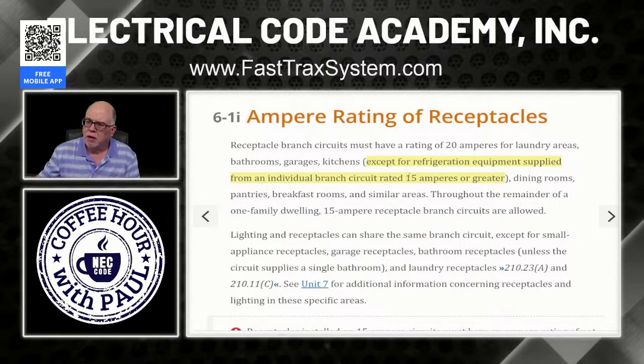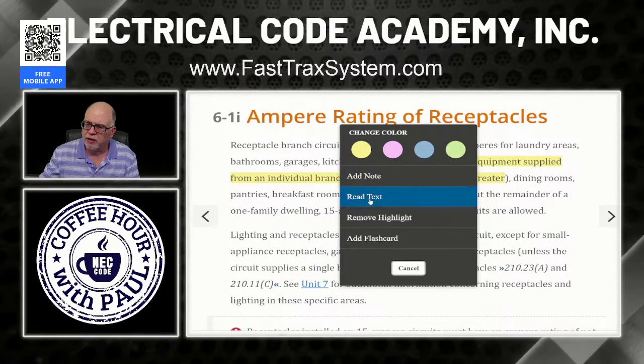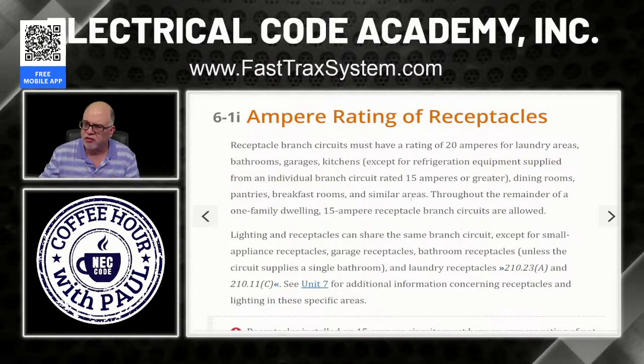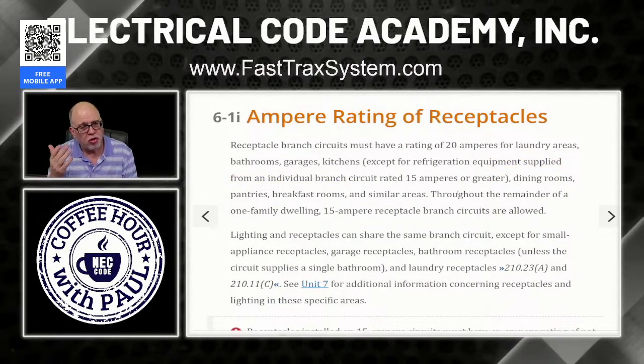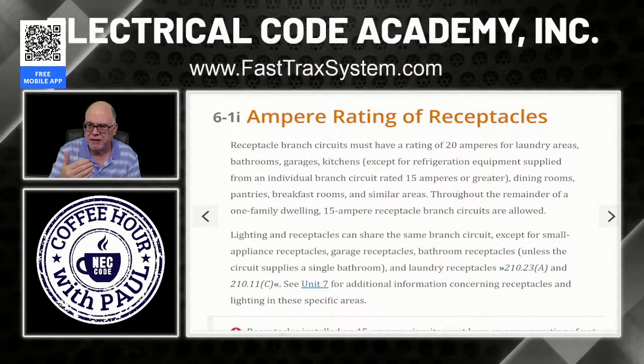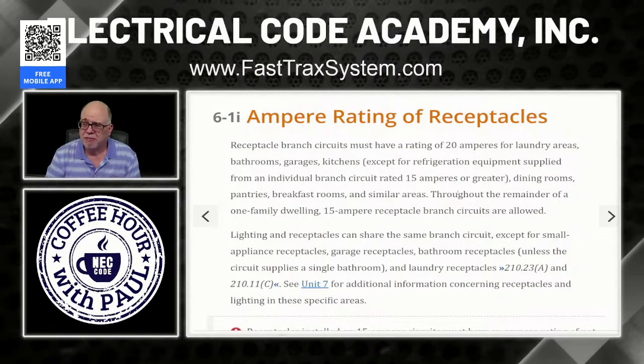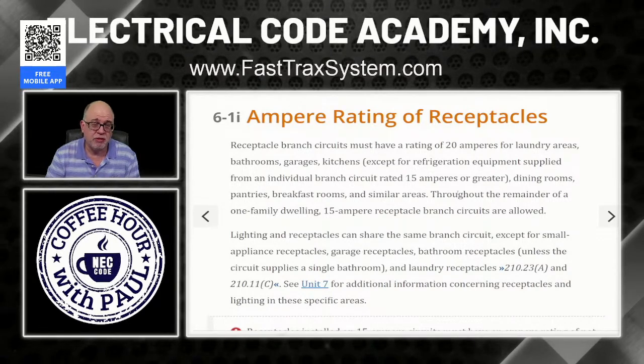Now, those are required to all be 20, except for the individual branch circuit to the refrigerator, if you choose to do that in your design. If not, typically the refrigerator is supposed to be, it says that in the code, on the small appliance branch circuit. But there is an allowance for it not to be, right? And that's under the exception, and that's where it could be 15 amps.